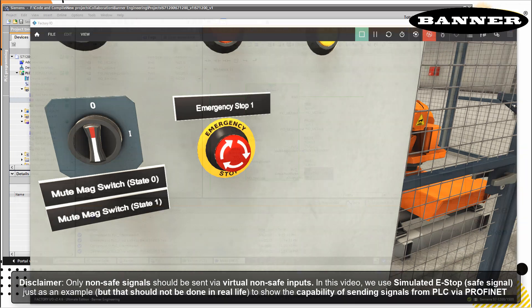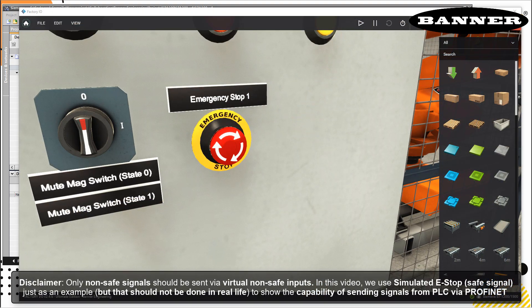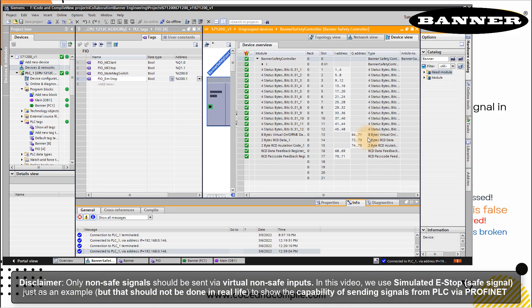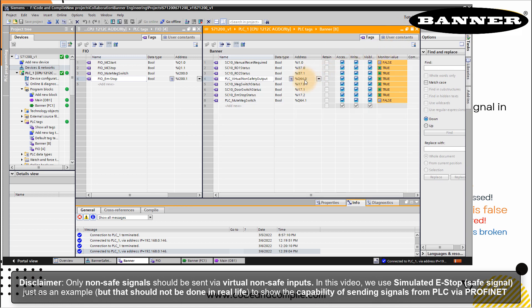I want to show you why. If you go back to your networks from the last video, here we can also take an output. I took the first output which shows as virtual on/off status — q64.0. So I took q64.0 in my PLC program. You have to remember that. This is my output in my PLC tags, and this is going to the safety controller. We have to use this information in the program to trigger the circuit with the e-stop from the virtual environment. Let's see how we can do that — it's very easy. We know we have an output q64.0, and now let's see how to use that in the safety controller.